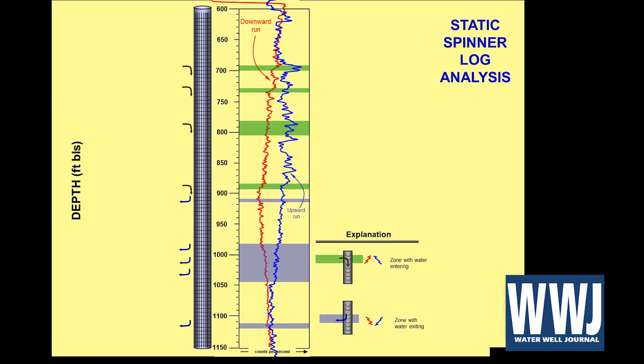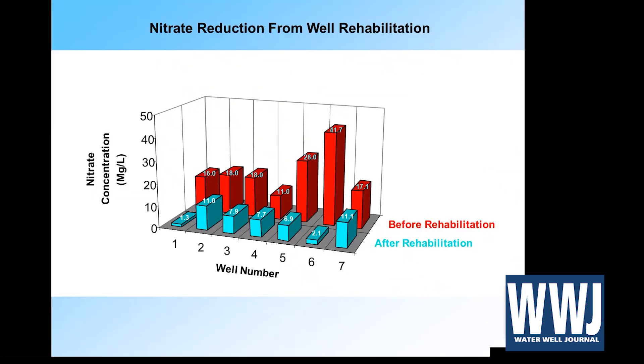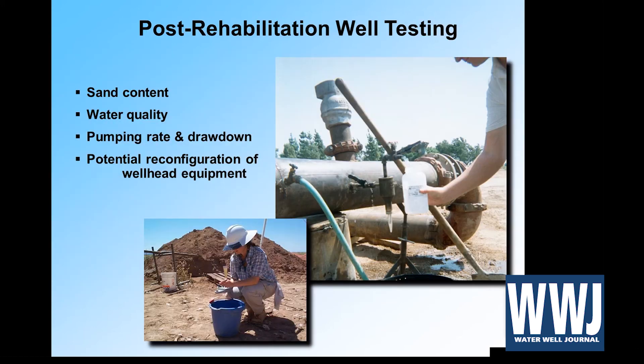This is a bit of a track record — it depends on local situations, but this shows nitrate results before in red and after in blue, with different amounts of improvement depending on the well and local hydrogeology. You can make things better. But once you've modified a well — put a liner in or used inflatable packers — you want to do some retesting, because now you've changed everything: the hydraulics, your pump may be off its curve. You just want to re-understand your situation, so a little testing is a good idea.